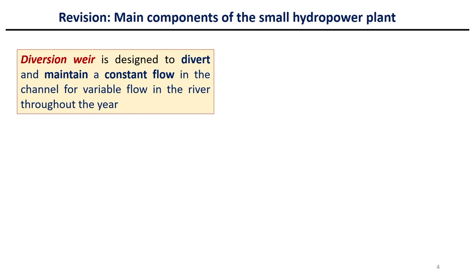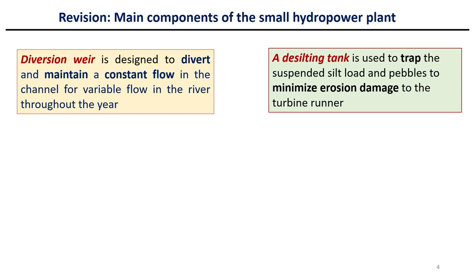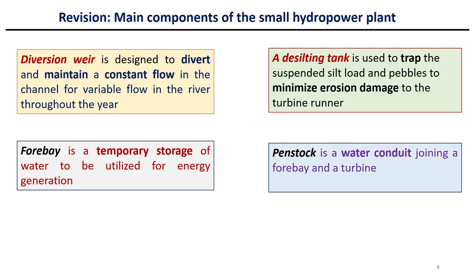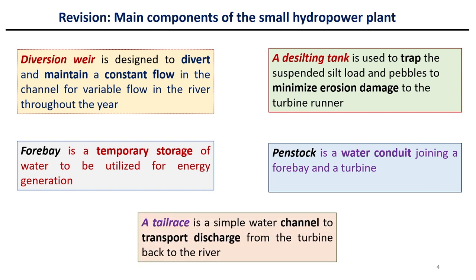The diversion weir is designed to divert and maintain a constant flow in the channel for variable flow in the river throughout the year. A de-silting tank is used to trap the suspended sediment load and pebbles to minimize erosion damage to the turbine runner. The forebay tank is a temporary storage of water to be utilized for energy generation. A penstock is a water conduit joining a forebay and a turbine. A tailrace is a simple water channel to transport discharge from the turbine back to the river.